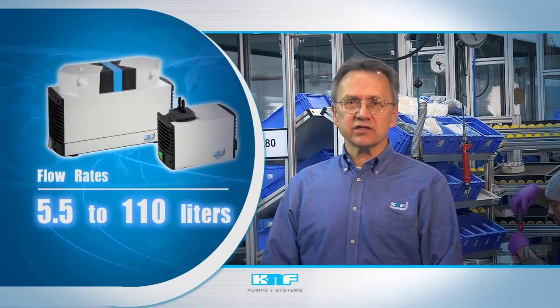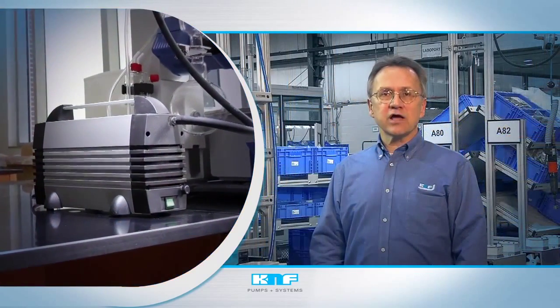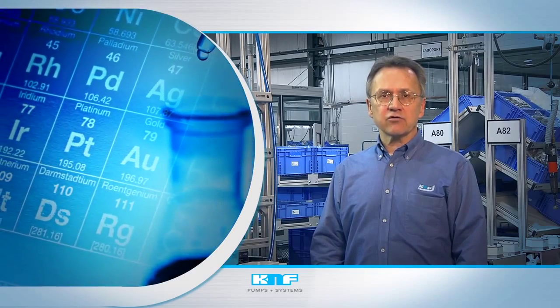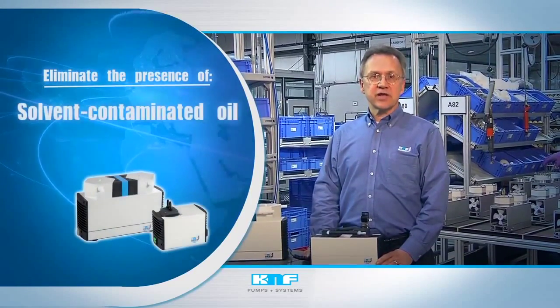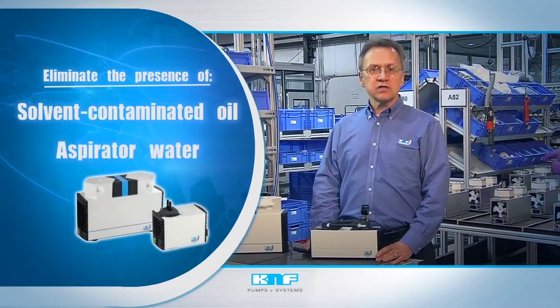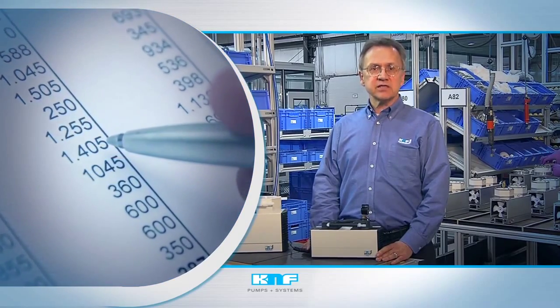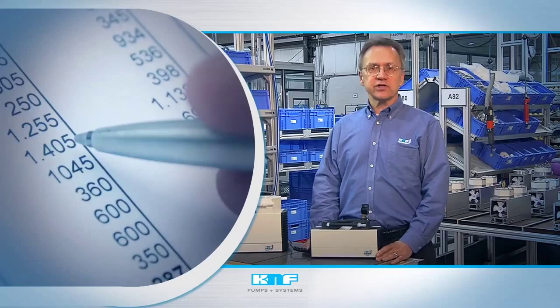Specifically, our oil-free, corrosion-resistant pumps offer flow rates from 5.5 to 110 liters per minute, with end vacuums as deep as 1.5 torr. This performance and reliability is matched by their ability to drastically reduce your lab's environmental footprint. Not only do they eliminate the presence of solvent-contaminated oil and aspirator water, they also provide significant cost-of-ownership benefits, as maintenance and disposal time is virtually eliminated.